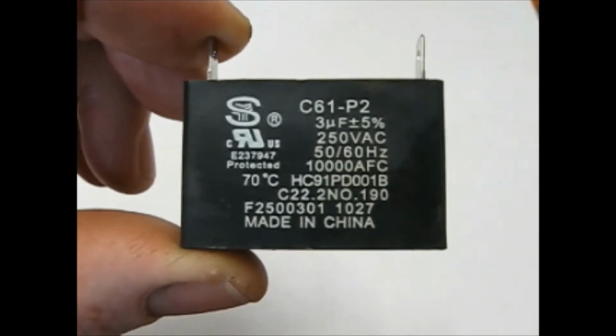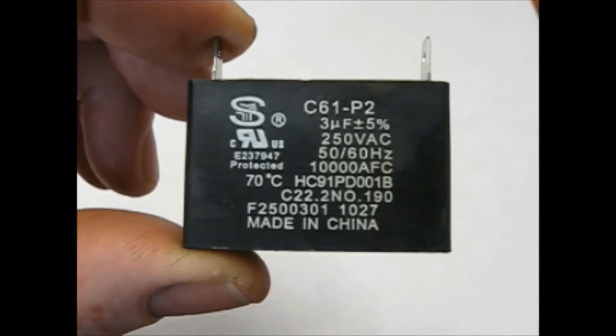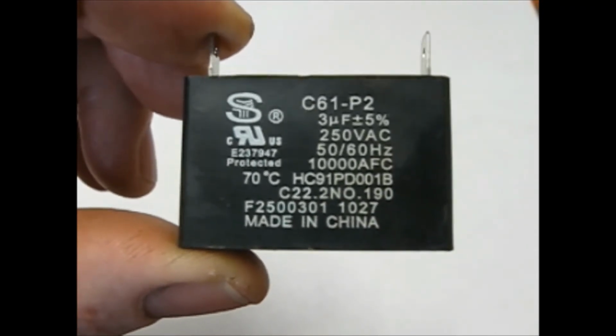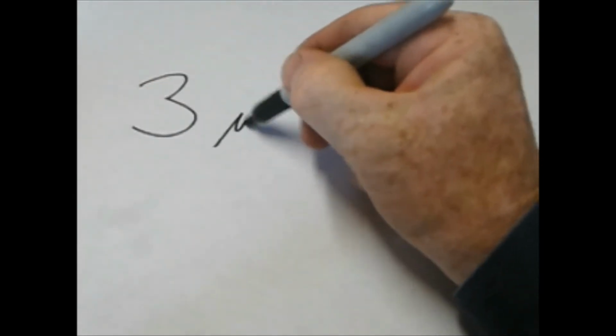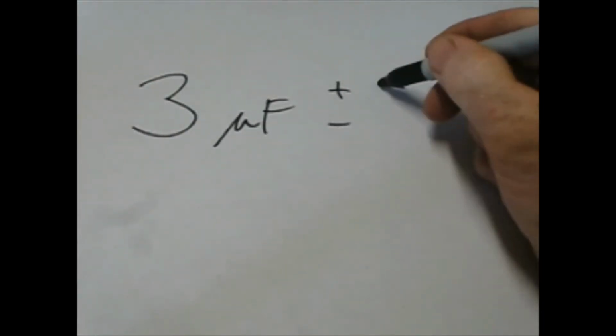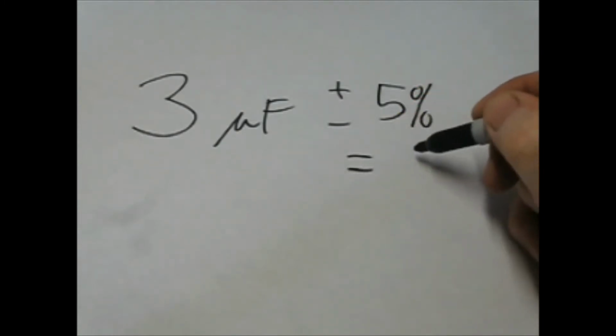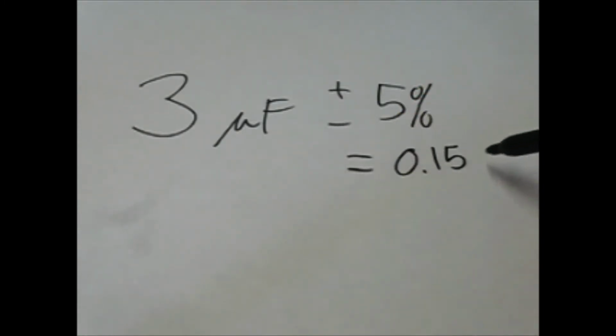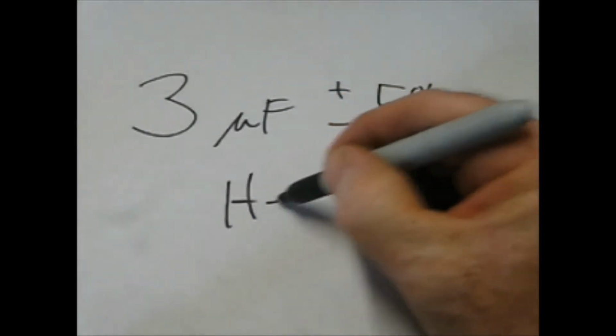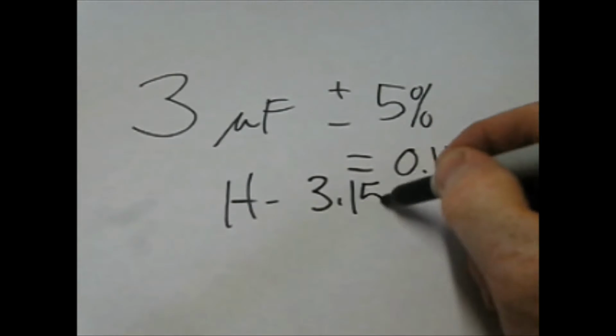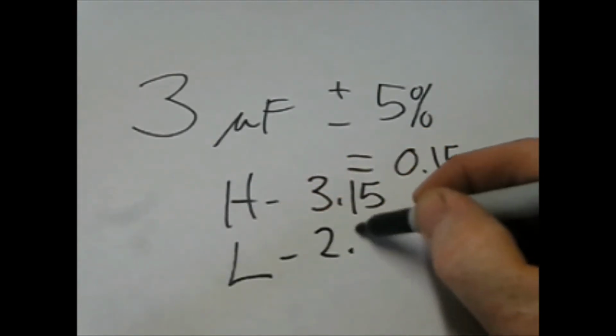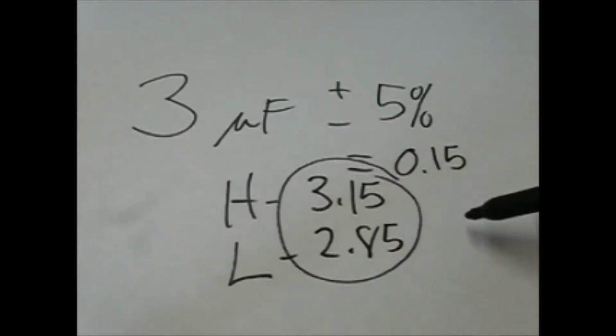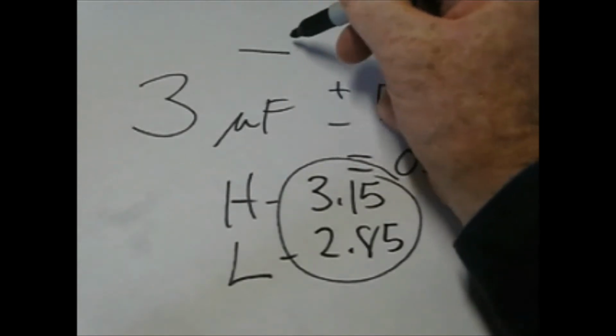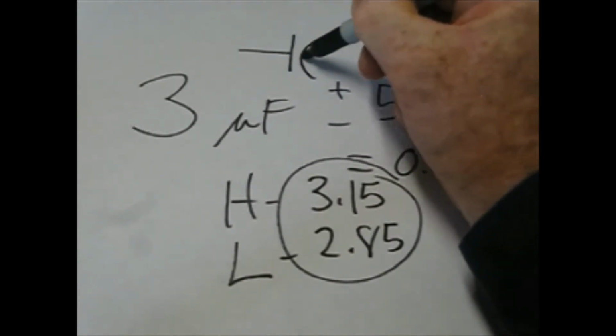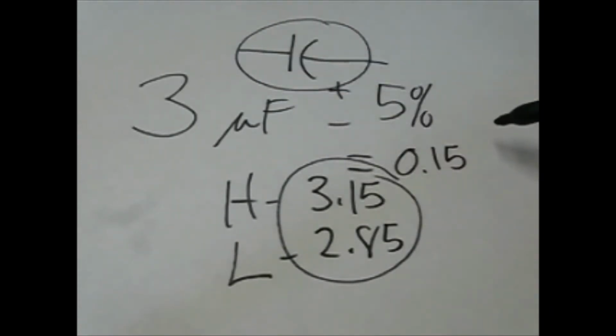This capacitor, also known as the start capacitor, is 3 microfarads plus or minus 5%. So we have 3 microfarads plus or minus 5%. 5% equals 0.15. So on the high end, we're looking at 3.15. On the low end, we're looking at 2.85. This is where our readings have to fall. And just one other note, on a meter, you're looking for a symbol that looks like that. That is a symbol of a capacitor.